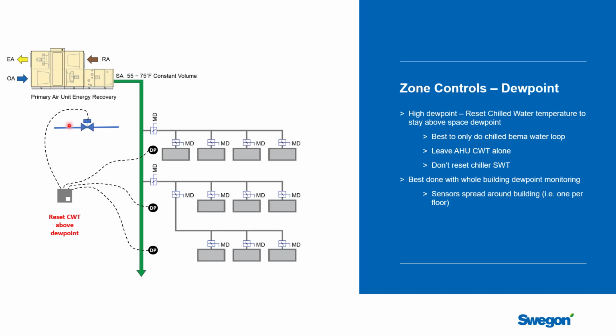And we would suggest that you only reset the chilled water to the loop that's going out to the chilled beams. Don't reset the temperature at the chiller, because that will warm the water that's going out to the air handling units, which you need to keep cool right now so that you can dehumidify the building. So just do the loop that services the chilled beams.